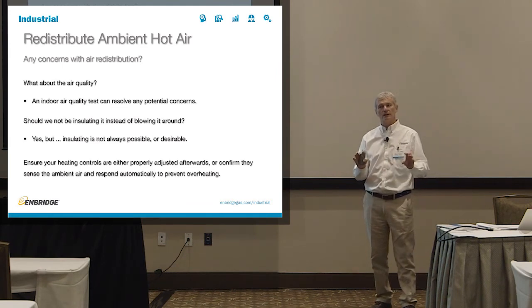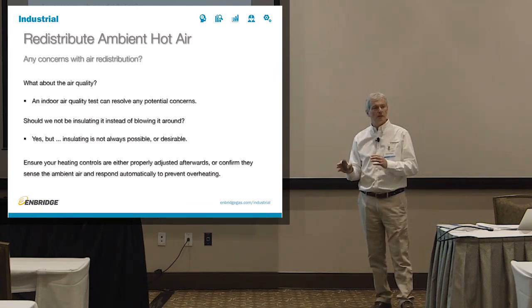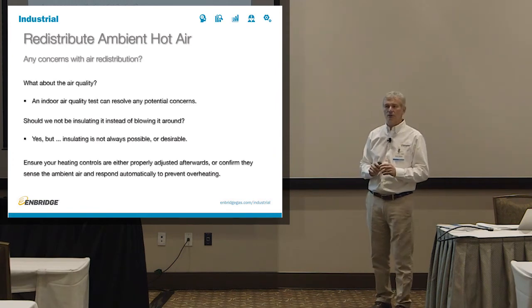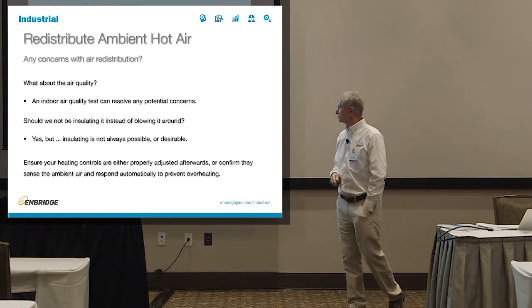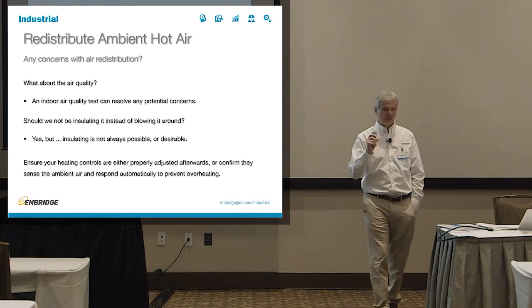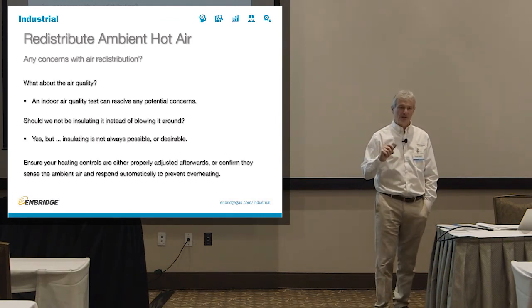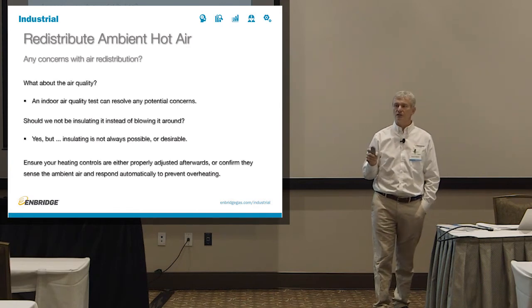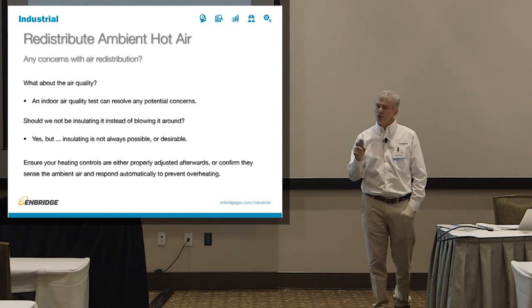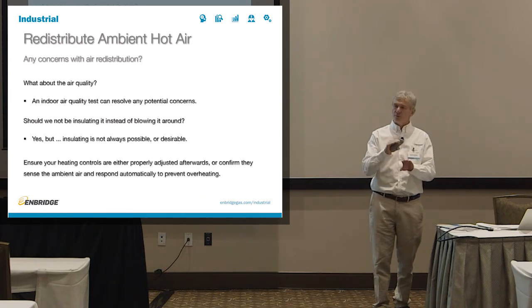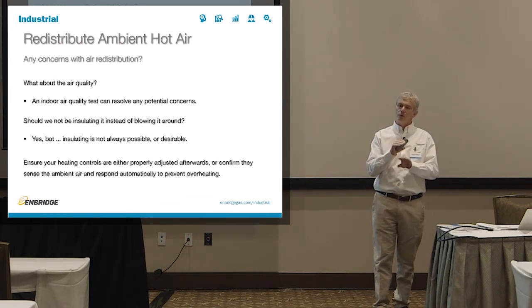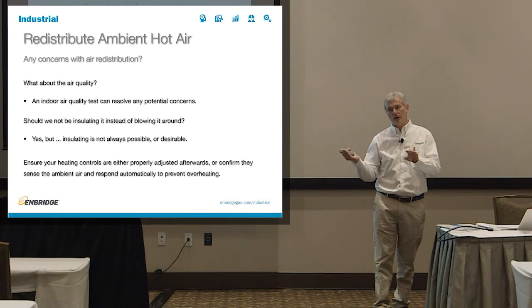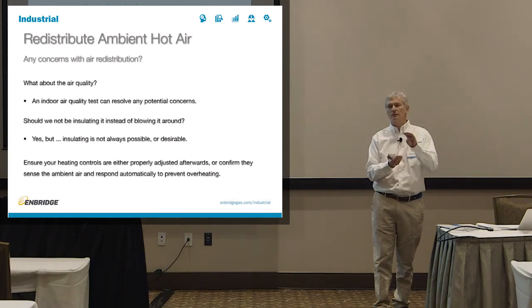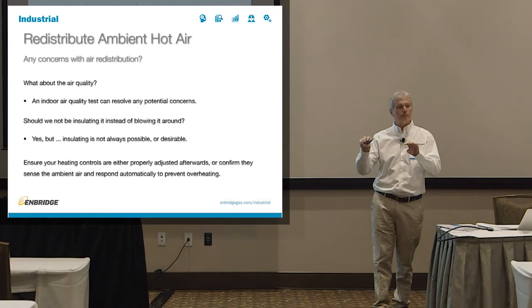So if you insulated all the stuff you can and you still have this waste heat, then you can use it by redistributing it around your facility. The other thing is, you will get people who will redistribute this hot air around, but they will never change any of their settings. And what will happen is your facility will get warmer as a result. And if your facility was on the borderline of being too cold in the wintertime, that's okay. But if your facility was already at 18 degrees Celsius and now you want to add heat and you're at 21 degrees Celsius, you may want to turn down your heating system.